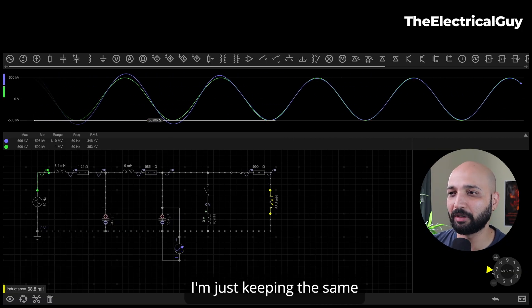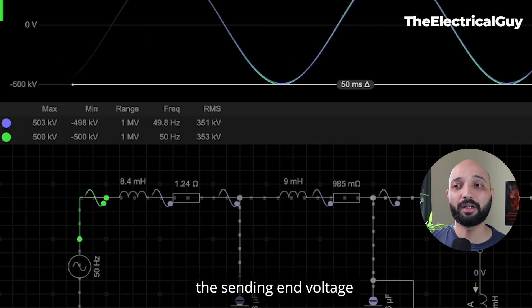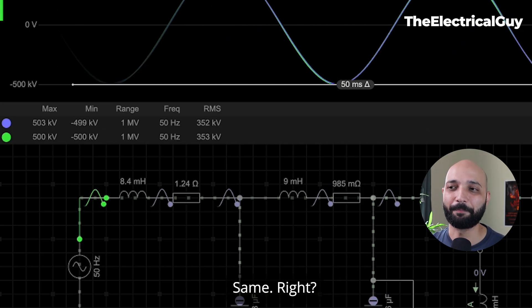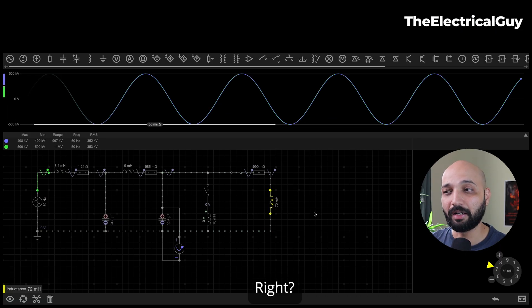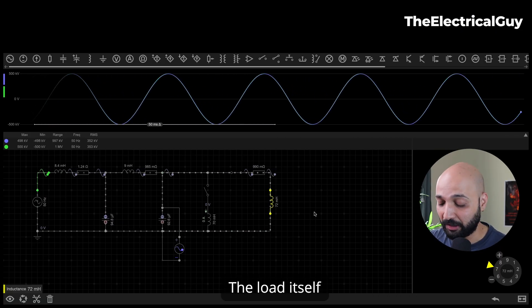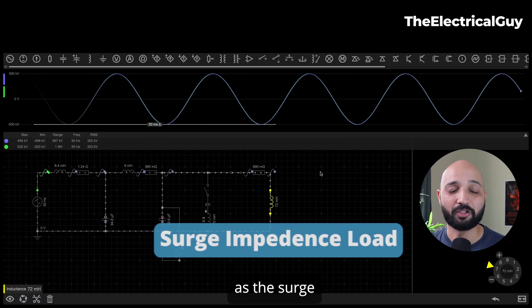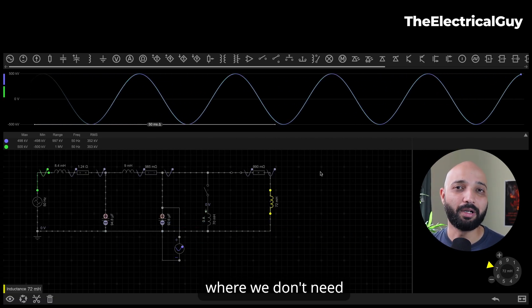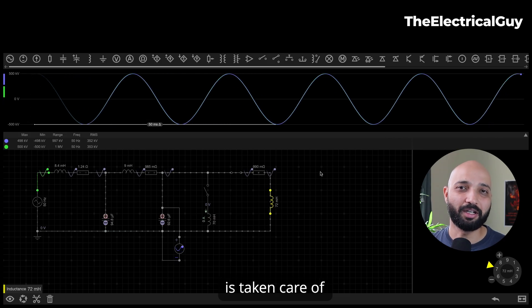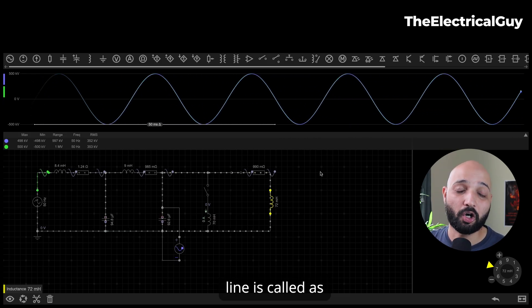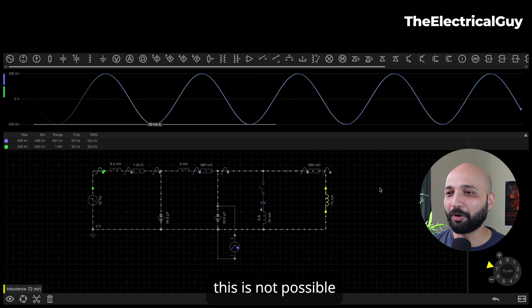Increasing just one load parameter for simplicity — and now almost the sending end and receiving end voltages are identical. We have not added any reactor, capacitor banks, or any other means of compensation. The load itself is compensating the line and taking care of voltage regulation. This particular load is what we call the surge impedance load — where we don't need any additional compensation; the load itself handles voltage regulation. This type of transmission line is called a self-compensated line.